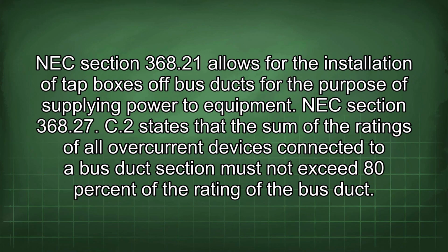NEC Section 368.21 allows for the installation of tap boxes off bus ducts for the purpose of supplying power to equipment. NEC Section 368.27 C2 states that the sum of the ratings of all overcurrent devices connected to a bus duct section must not exceed 80% of the rating of the bus duct.